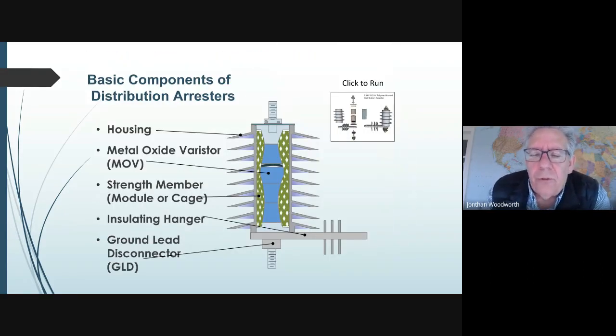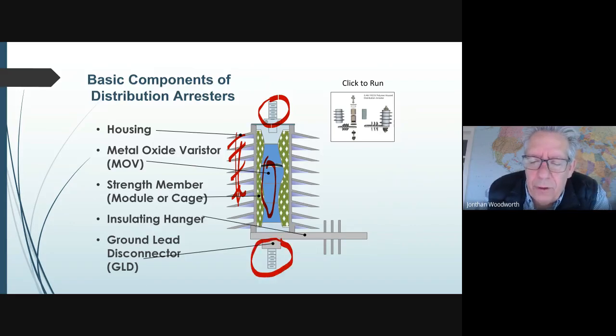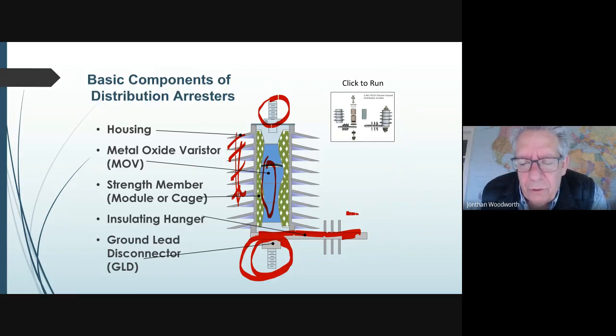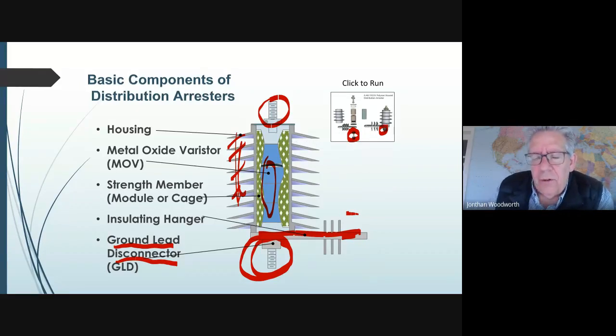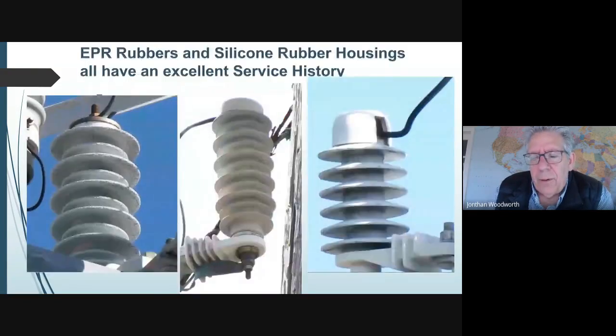Here's what the distribution arrestor looks like. It has the MOV blocks on the inside, rubber housing on the outside, the top terminal, a bottom terminal, which is a little bit different than a station arrestor. I'll tell you about that in a second. And then usually has a plastic hanger to hold it in place. This section on the bottom of a distribution surge arrestor has a ground lead disconnector built into it. There are different forms of it, but it looks different in some places. But it's usually a disconnector that's used to disconnect the arrestor only one time at the end of life. And I'll talk about that again in a second.